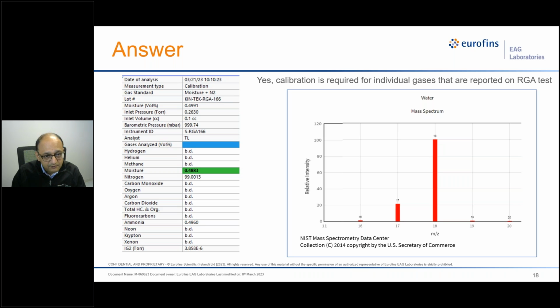But for example, if I have to find out the ammonia content in the same gas, then I would be looking at mass 17. But moisture would interfere, also generating mass 17. So how do I calibrate for that? We use the moisture calibration for that. What we determine, without any ammonia in the standard gas, which is my daily calibration, is the contribution of moisture on mass 17, and that contribution factor will be used for determining ammonia. So the ammonia determination is based on the measured mass 17 minus the contribution from the moisture, and the leftover signal can be assigned to ammonia. So that determination is also made through the calibrations.